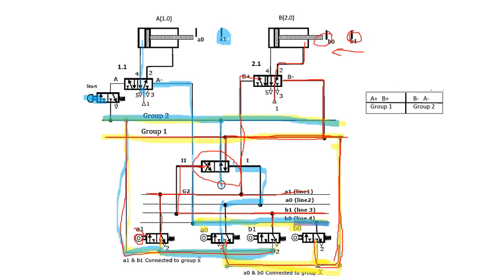The B0 signal provides an input to memory valve 1.1. Memory valve 1.1 then supplies air to the rod end of cylinder A, causing cylinder A to retract. When cylinder A retracts fully, A0 is hit. A0 changes the group supply itself — switching the supply from group 1 back to group 2. Group 2 is now connected to the limit switches A1 and B1, and also has the start button connection. So until the start button is pressed again, the next sequence will not start. This is how the cascade method works.